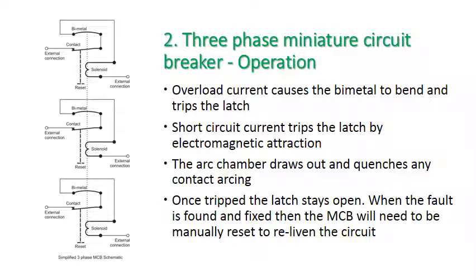So how does a three-phase circuit breaker operate? The first thing is, if there's a fault in any one of the phases, all three are tripped together. And as you saw in an earlier slide, there's that bar that goes through the middle of the circuit breaker that connects all three trips together. So if you have an overload current in one or more bimetal strip, the bimetal heats and starts to bend, and eventually, if the overload is maintained, the mechanism will be tripped and the circuit breaker will stop the current flow. At this point, there's not enough magnetism in the electromagnetic trip mechanism, or the solenoid in this picture, to cause the trip to happen.